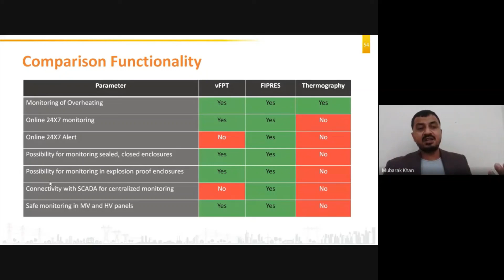Connectivity with SCADA for centralized monitoring, you can do in FIPRES, you cannot do in vFPT or in thermography. Okay. Safe monitoring in high voltage and medium voltage panels. Safe monitoring is possible with vFPT and FIPRES, but not with thermography, because if you open the panel for doing the thermography, you are already compromising the safety of the human who is taking the image. Okay, that is why it is not safe in thermography.